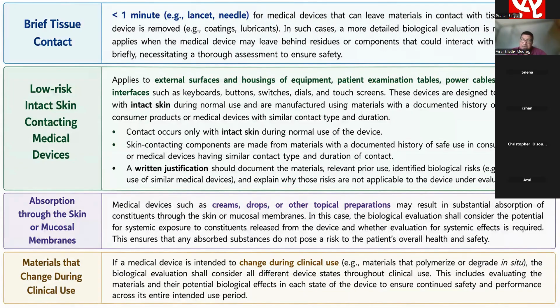So we have to identify all the possible hazardous situations and materials present in our medical device before conducting the biocompatibility test, to define whether any requirement for other biological tests is applicable to me or not. It also talks about identifying the requirement of the ADME study, that is mainly for absorption, distribution, metabolism, and excretion.